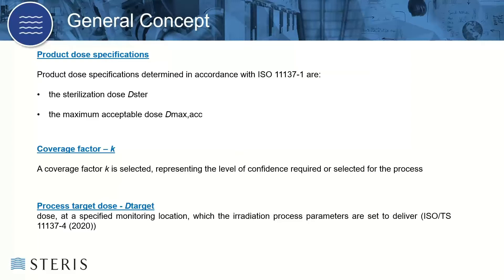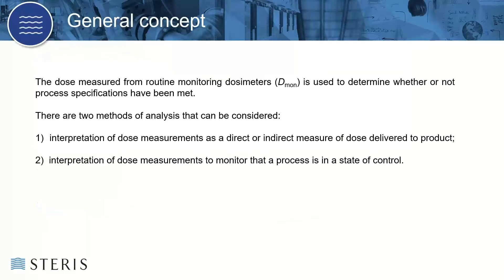The end result is the sterilization or minimum and maximum acceptable dose. Next, we'll look at coverage factors. Coverage factor, also represented by the letter K, represents the level of confidence that is required or selected. For example, K equals 2 is a 95% confidence level, also expressible as two standard deviations. Process target dose is the dose at a specified monitoring location which the irradiation process parameters are set to deliver. The dose measured from routine processing — the monitoring dose — is used to determine whether or not the process specifications have been met.